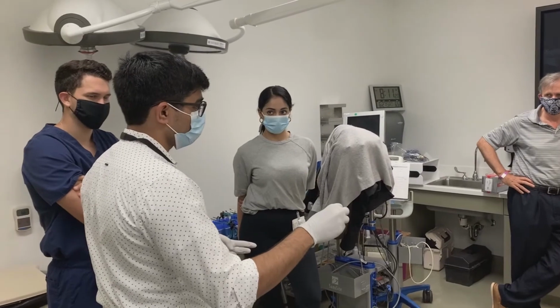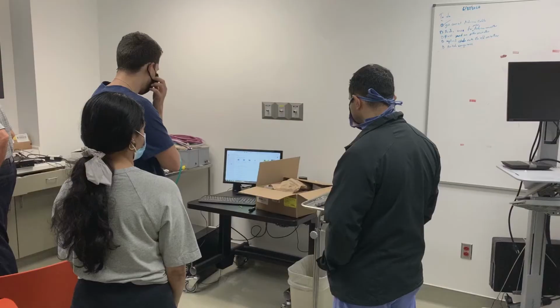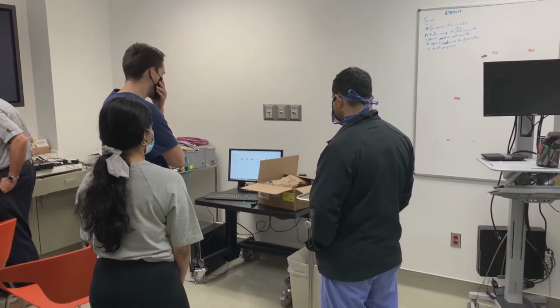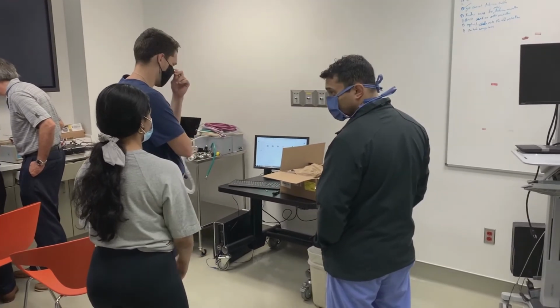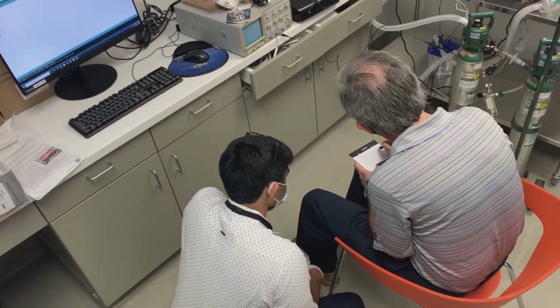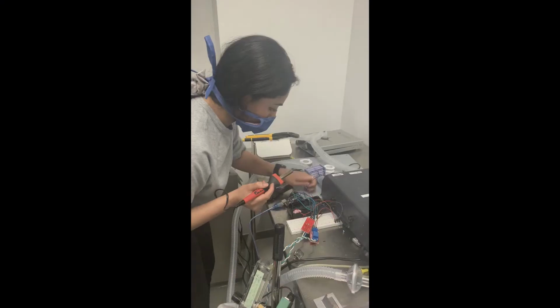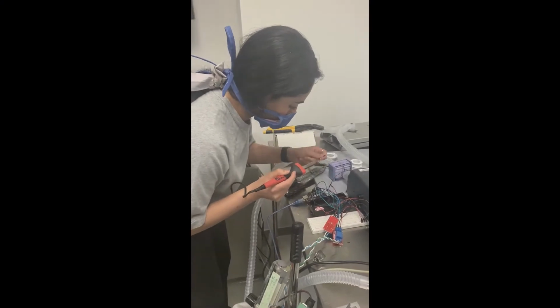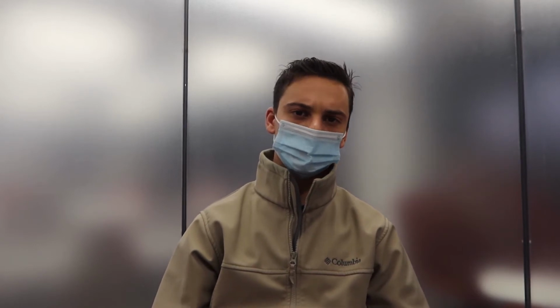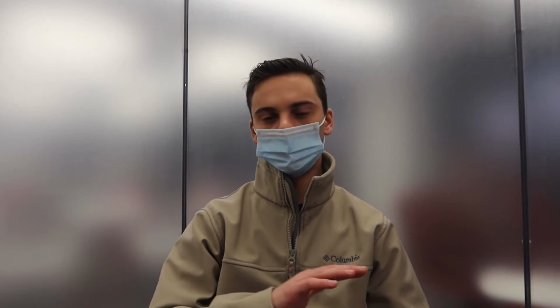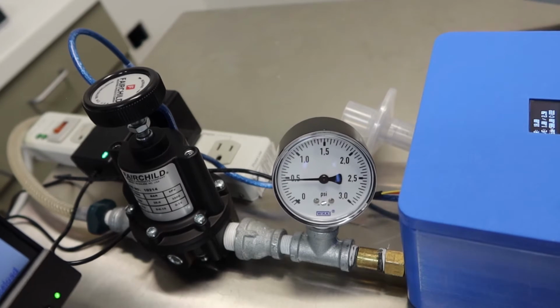When we joined the team, they needed help with the computer science and electrical engineering aspects of the project. They were having trouble getting the exact timing for opening and closing of the solenoid valves. And this is important to ensure that we can get the predicted tidal volumes and that there isn't pressure buildup in the system. So one addition that the EnMed engineers made to the overall project was we put in a pressure regulator valve that is able to hold the whole pressure of the system below half a psi, which is really important because we don't want to overpressure the system.